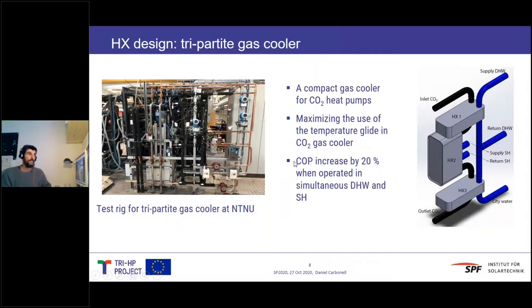Another development is what's called a tripartite gas cooler, a compact gas cooler used in CO2 heat pumps, where the goal is to maximize the temperature glide in the CO2 gas cooler. With these developments, we are able to increase the COP of the heat pump by 20% when operating in simultaneous domestic water and space heating.